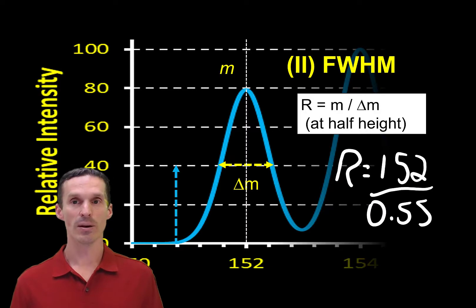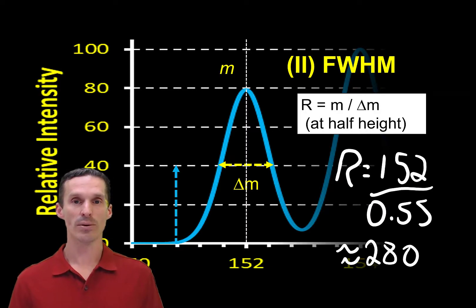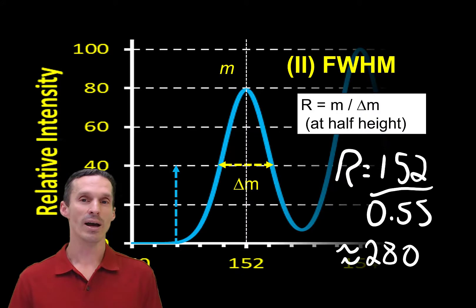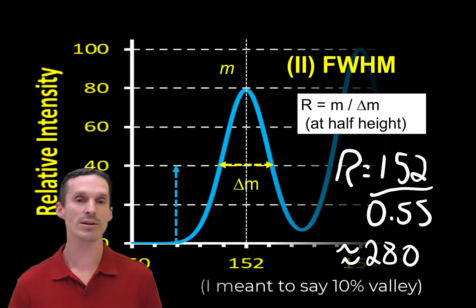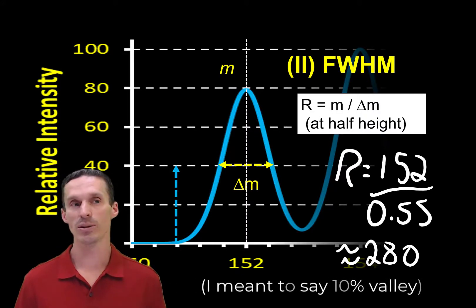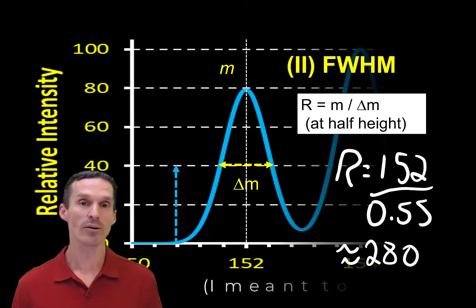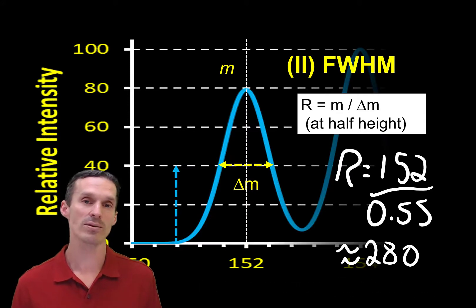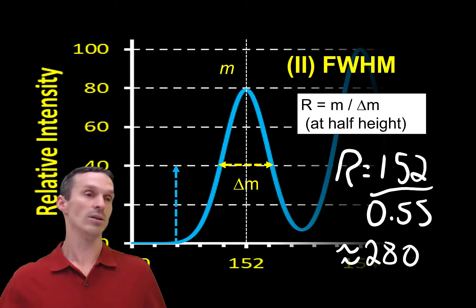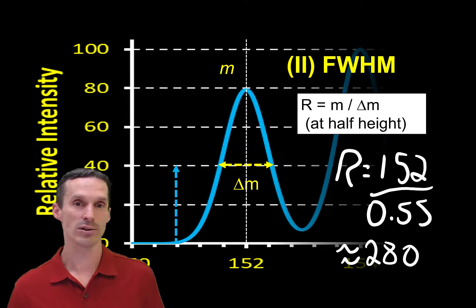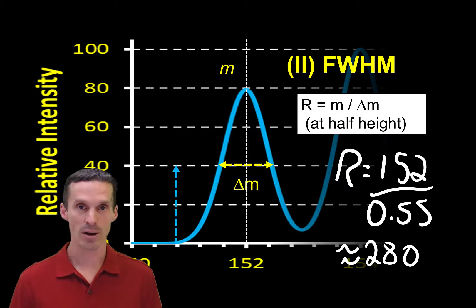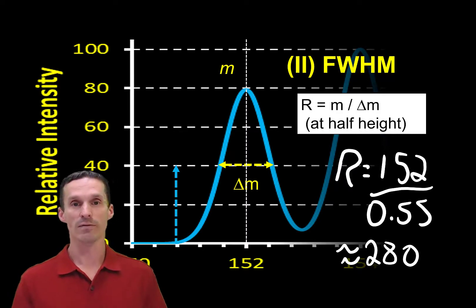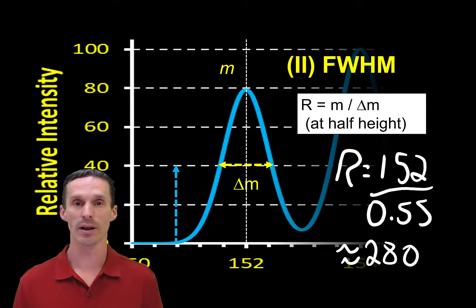So that's the number we get here. Notice that the number isn't even the same as with the 10% valley definition, so there is a relationship between the two. You need to know how you're defining resolution and not just say 'the resolution is X.' Usually people say 'resolution [full width at half maximum].' This is the most common one you'll encounter.